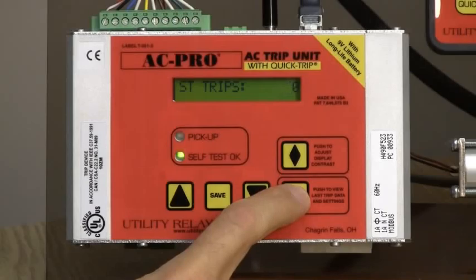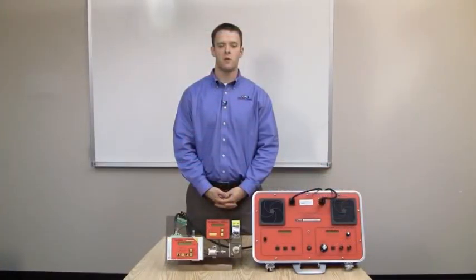Once the trip counter is displayed on the LCD, continually pushing the review button will step through the various trip counts. After the trip counter, pushing the review button will step through the AC Pro settings. As I mentioned previously, without using the key, the settings can only be viewed and not changed. For more information on reviewing trip data and the settings on the AC Pro, please see the programming video on our website. After doing a test as we just did, it is very important to clear the last trip data so it will not confuse operating personnel.